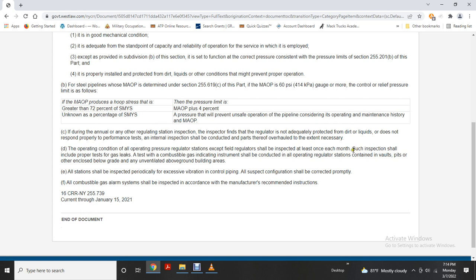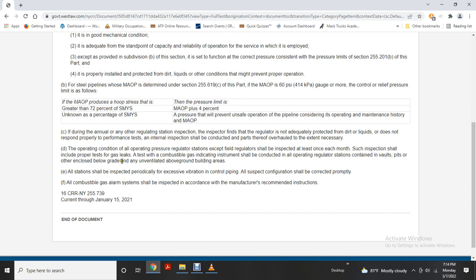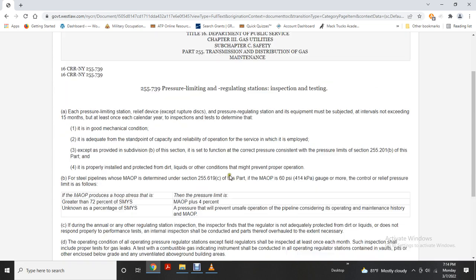Such inspection shall include a proper test for gas leaks, and a test with a combustible gas indicating instrument should be conducted for operating regulator stations containing vaults, pits, other enclosed below-grade areas, and unventilated above-ground building areas. All stations shall be inspected periodically, for excessive vibration in control piping. All unsatisfactory conditions shall be corrected promptly. All combustible gas alarms shall be inspected in accordance with the manufacturer's recommended instructions.